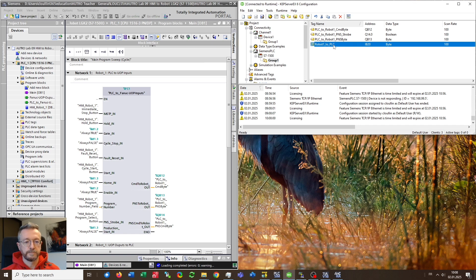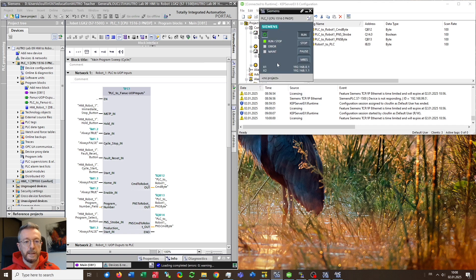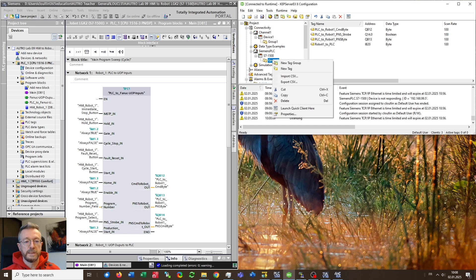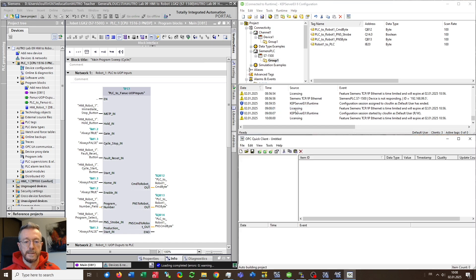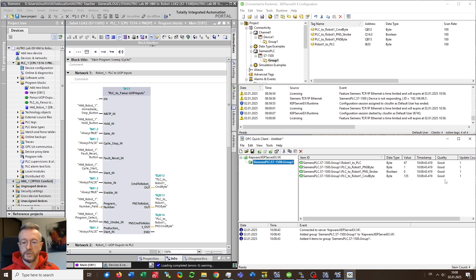Finally for the return path I am sending back to PLC SIM a byte which contains the status information of the robot and here we go. So this is the step where you would first like to check if the communication so far works because we have already started PLC SIM is running also our NAT to PLC SIM server is running. So by right-clicking on group and clicking launch quick client here you get this window where you can observe the exchange data and first thing you will look at is this column here quality which is good which simply means that the communication is working.